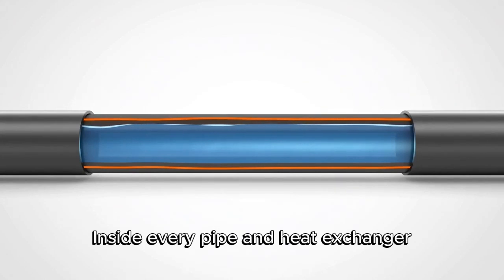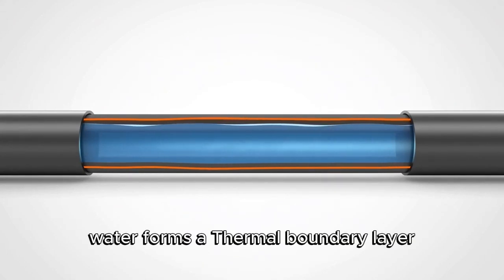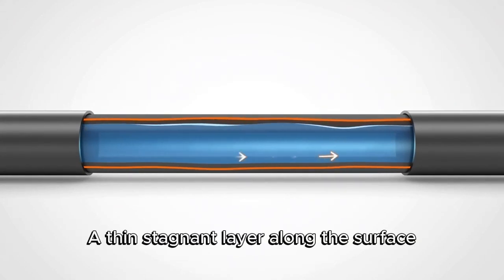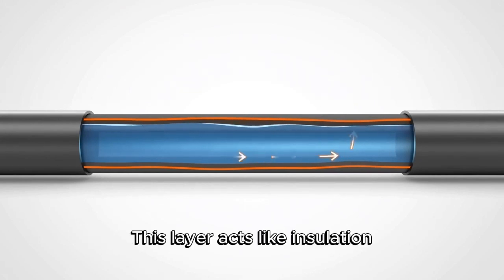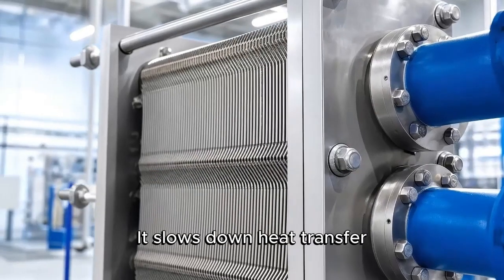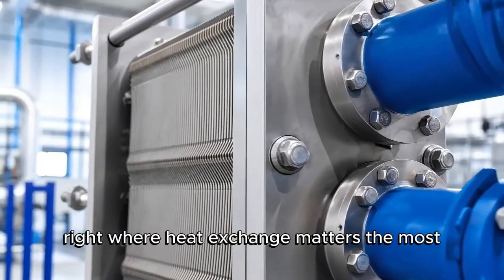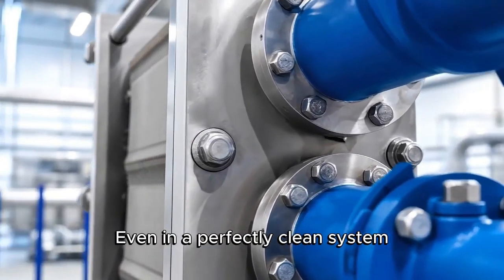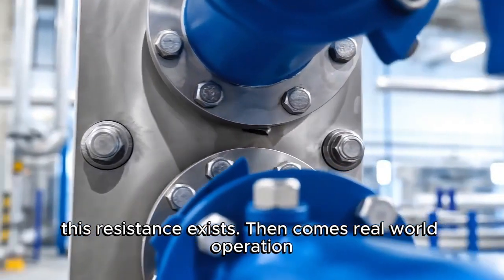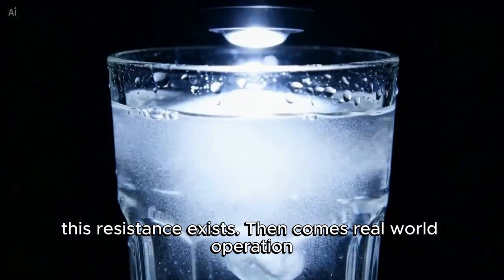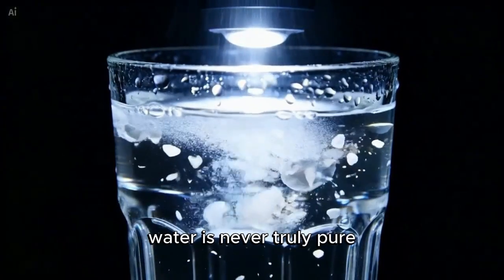Inside every pipe and heat exchanger, water forms a thermal boundary layer, a thin, stagnant layer along the surface. This layer acts like insulation. It slows down heat transfer, right where heat exchange matters the most. Even in a perfectly clean system, this resistance exists. Then comes real-world operation. Water is never truly pure.